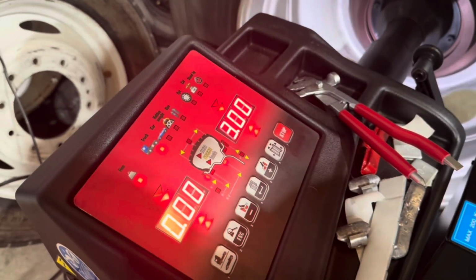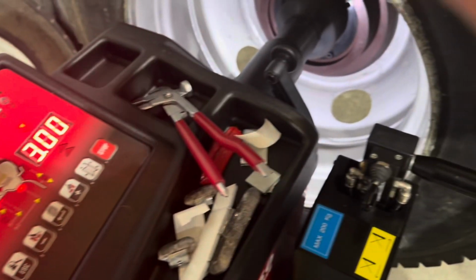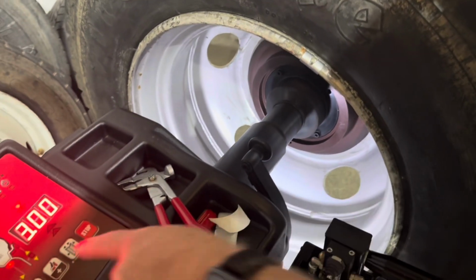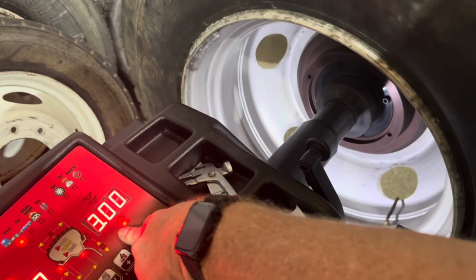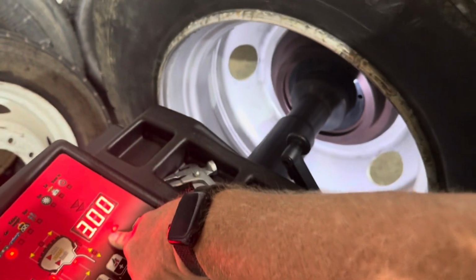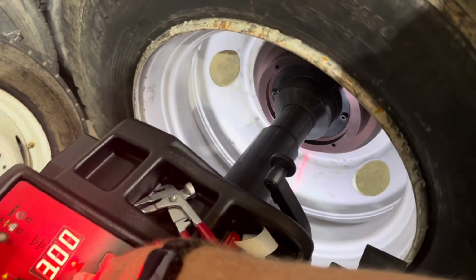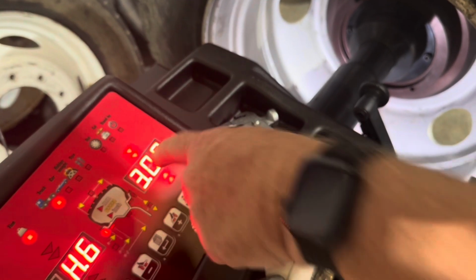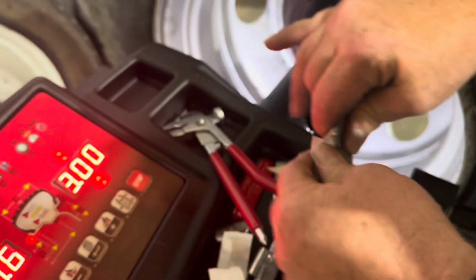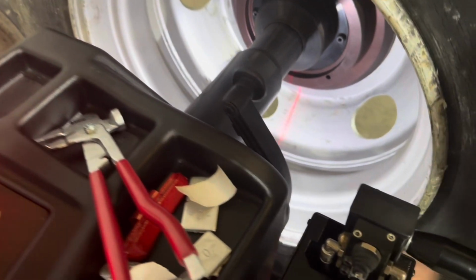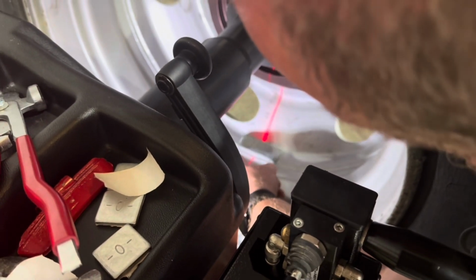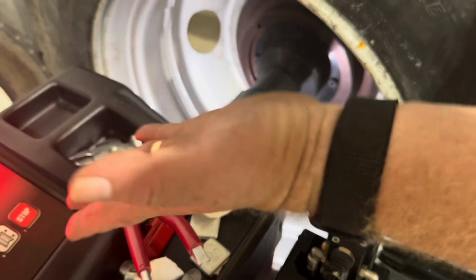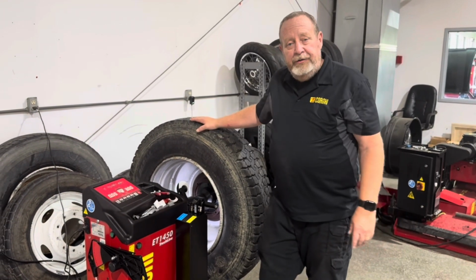Once I release that, it's calling for 3 ounces. It's a little more weight than what we had before because we're moving the weight inside. We're going to highlight that. And then you would simply take your 3 ounce tape weights, make sure that you center it 50-50, even if you have to split it down the middle, and then do your check spin. This is how you operate the ET1450.